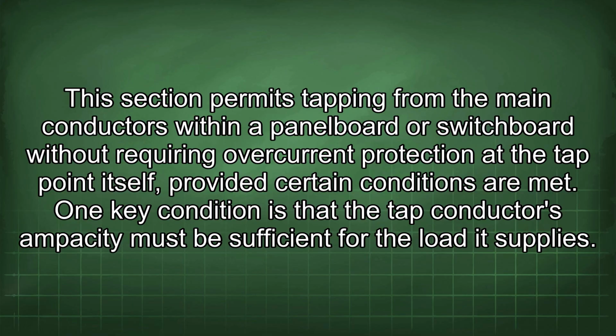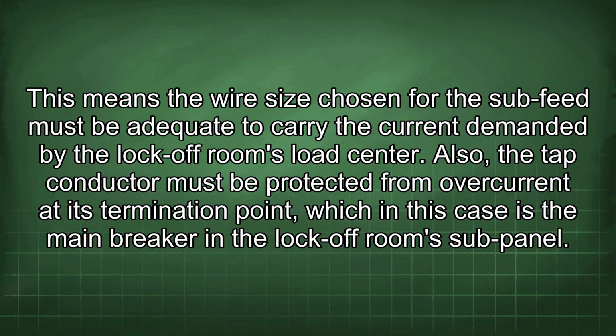One key condition is that the tap conductor's ampacity must be sufficient for the load it supplies. This means the wire size chosen for the sub-feed must be adequate to carry the current demanded by the lock-off room's load center. Also, the tap conductor must be protected from overcurrent at its termination point, which in this case is the main breaker in the lock-off room sub-panel.